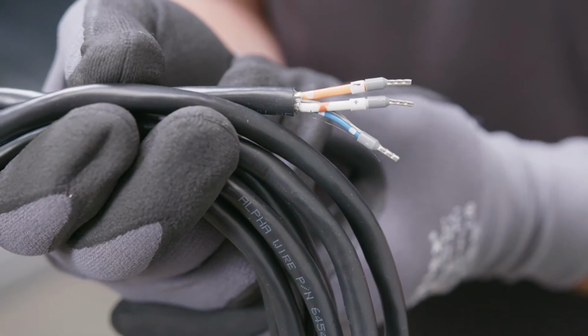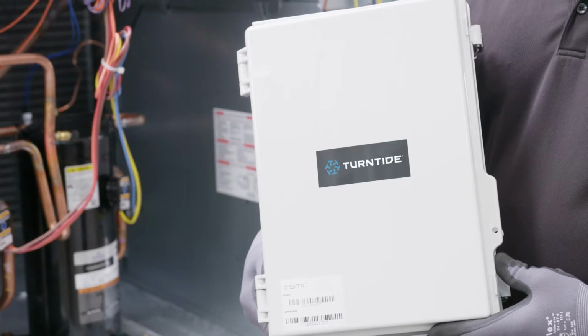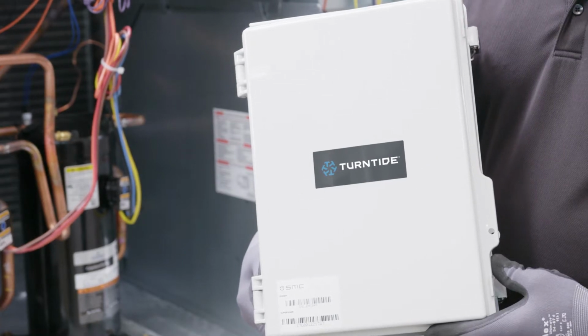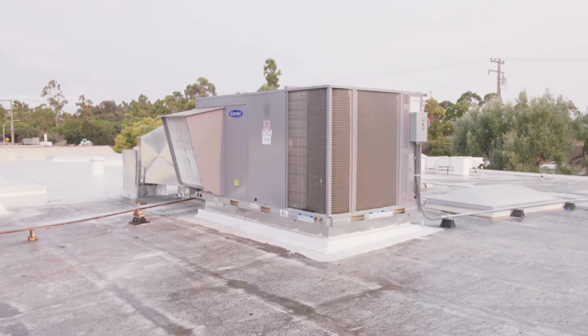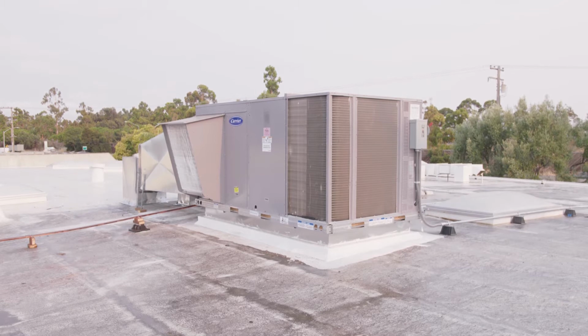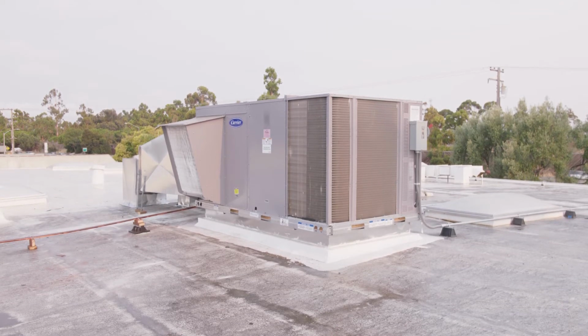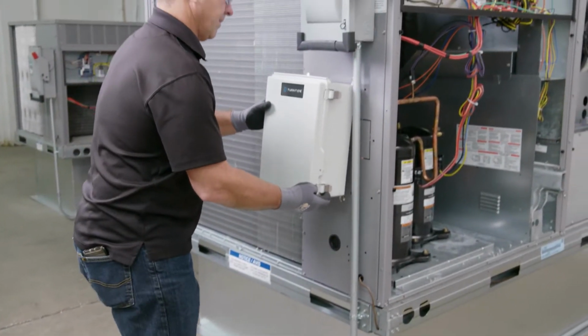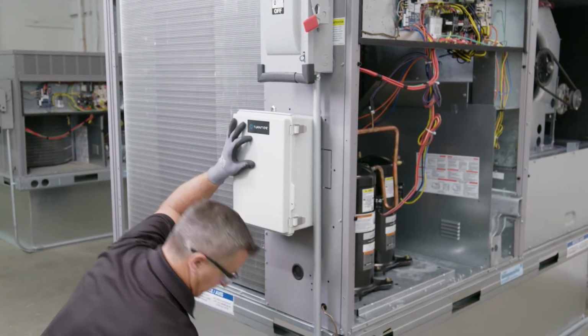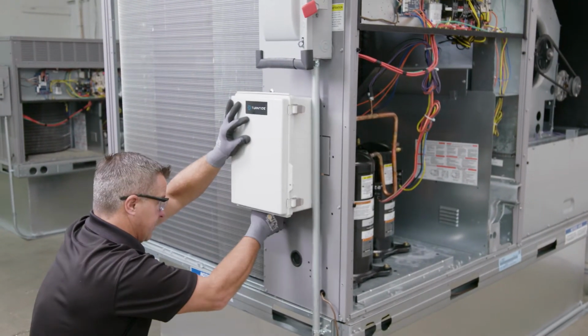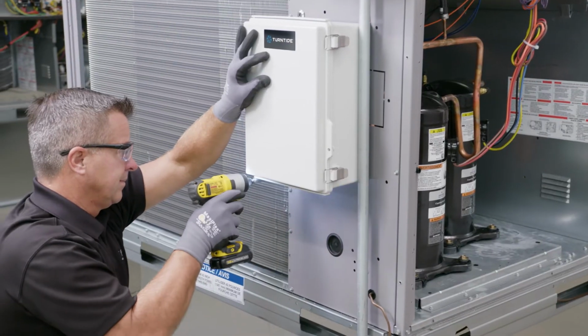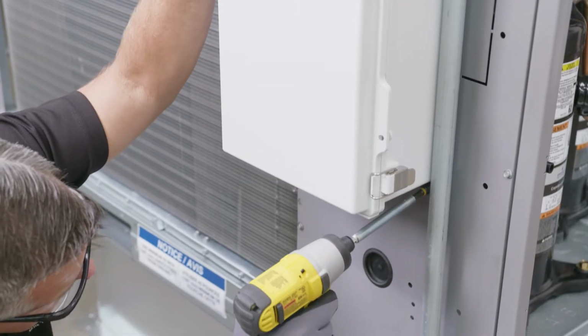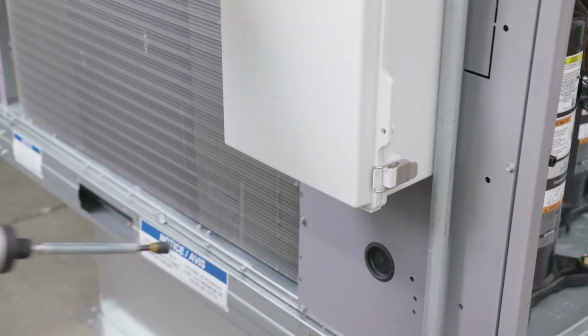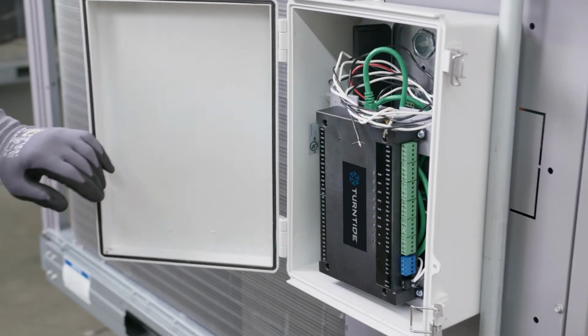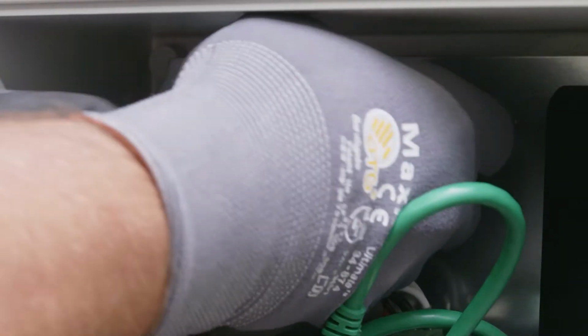The first step in installing the M&V Kit is deciding on the location to mount the weatherproof enclosure. Look around the unit and find a location that is suitable for the size of the panel and which will not prevent access to removing unit panels for normal servicing. The best location is normally next to the main power disconnect or near the unit control panel. Assuming there is ample room, mount the waterproof enclosure using the 4 external mounting tabs, which are included with the panel. You can use a through-mount conduit and run the wiring that will be required for the controls.